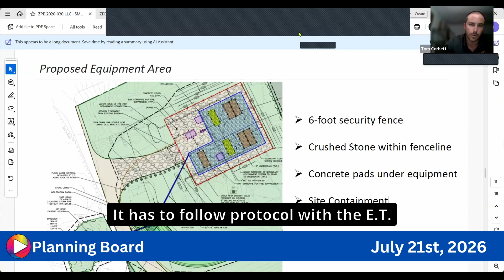So just remind me again, what triggers the closing of that valve out of the secondary containment? The secondary site containment valve closes upon 2 signals of a fire alarm, smoke alarm, heat alarm, or gas alarm. Okay. So each container has 2 heat alarms, 2 smoke alarms, and 2 gas detectors.